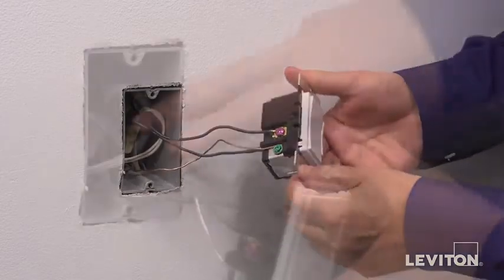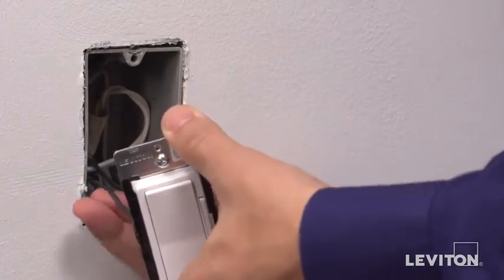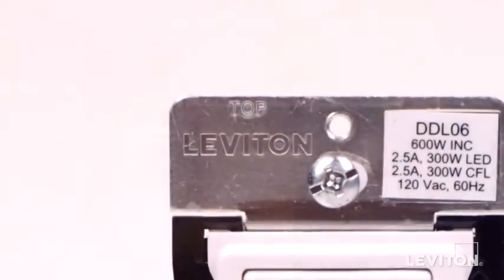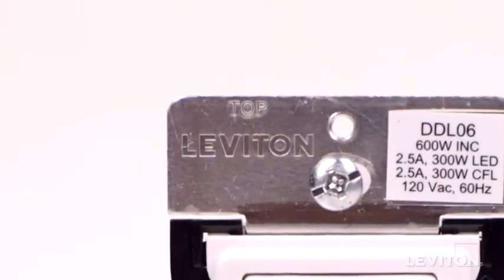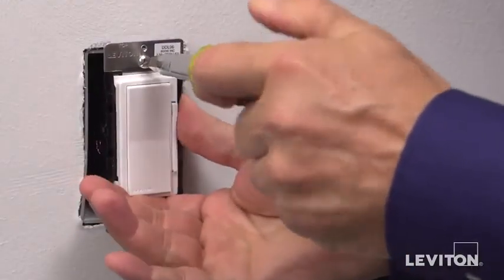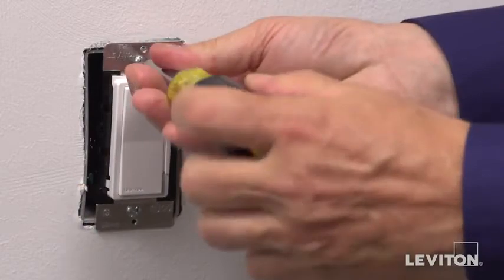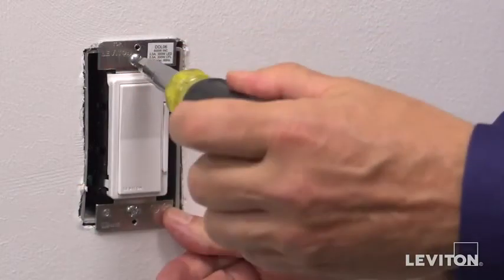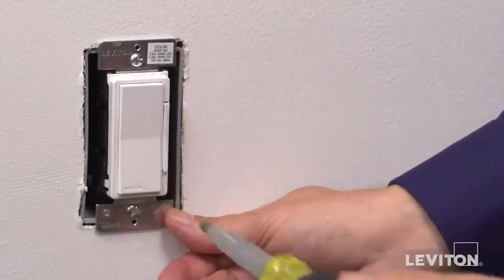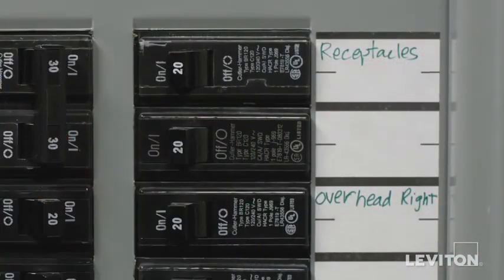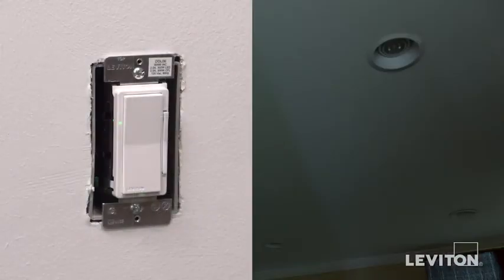Position all wires to provide room in outlet wall box for device. Ensure that the word top is facing up on device strap. Partially screw in mounting screws in wall box mounting holes. We are now going to test the dimmer. Restore power at the circuit breaker or fuse. Press pad until locator light is off.